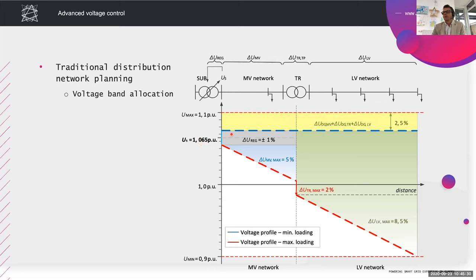You have the hysteresis, because the tap changer is not able to keep exactly the set voltage. And then you allocate bands for different voltage levels. You, for example, say, okay, the maximum voltage drop I allow in the medium voltage network is 5%. Then the maximum voltage I allow on the medium to low voltage transformer is 2%, and so on. The maximum voltage drop I allow in the low voltage network is 8.5%. And this is at maximum loading.